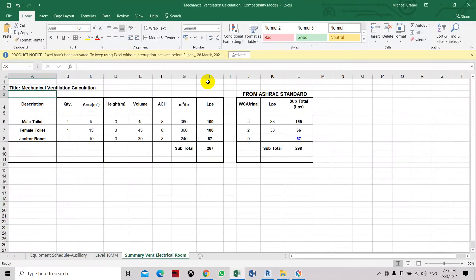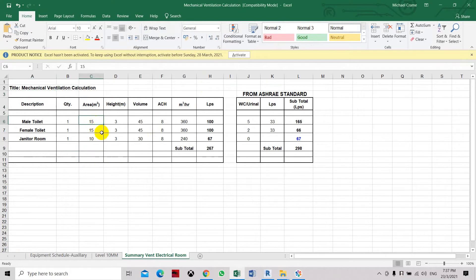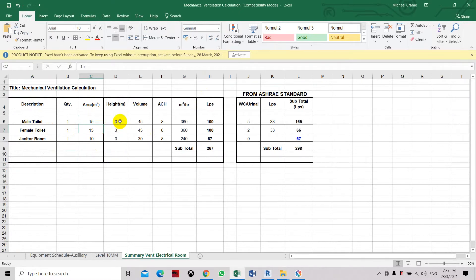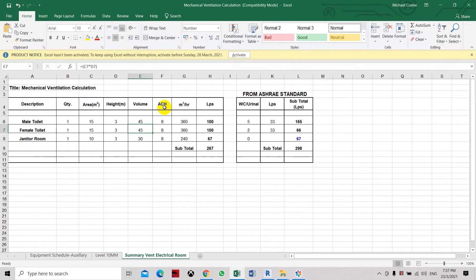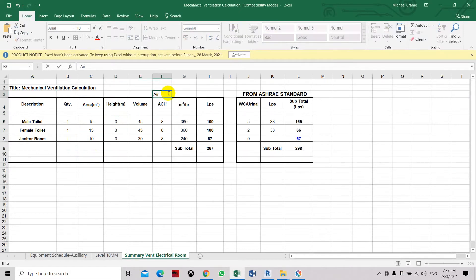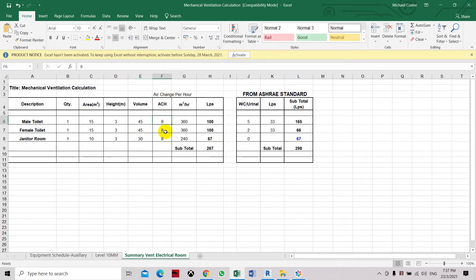So here I have a sample calculation. The toilet area is about 15 square meters. The male toilet and the female toilet is about 15 square meters. Volume height is about 3 meters. Volume is 45. Air change per hour, this one is 8.